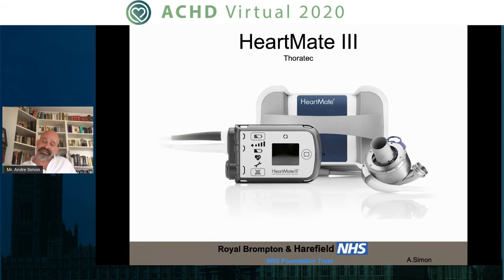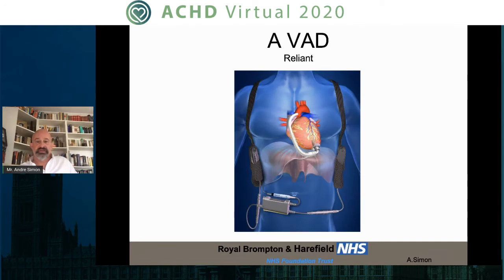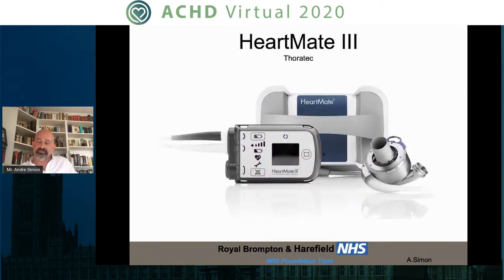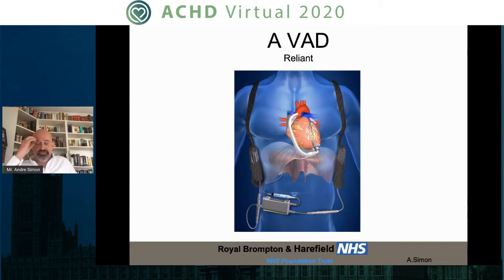This is a fully magnetically levitated device, very similar to the HVAD. It's a centrifugal pump. It's implanted in the same way, and there are many similarities. And of course, the companies also would like to point out differences between the devices, but there are many similarities. And the last one was the AVAD, which was, again, basically the Heart Assist 5 in a refashioned way. The interesting point about this device was that it had a telephone controller integrated into the controller here, so you could remotely access your patient's data anywhere where they had telephone access, which was quite sexy, because the patient could call you up and say, I got a problem, this alarm goes off, and you could then log into the device and see what's happening.